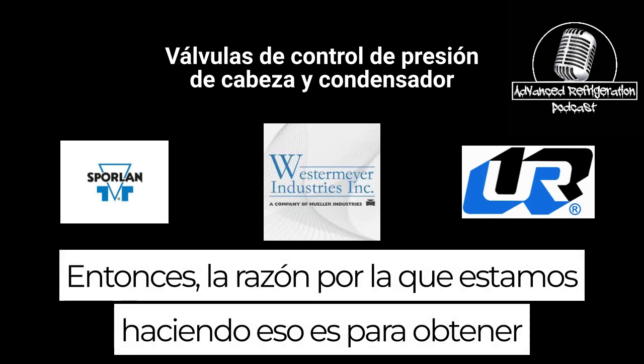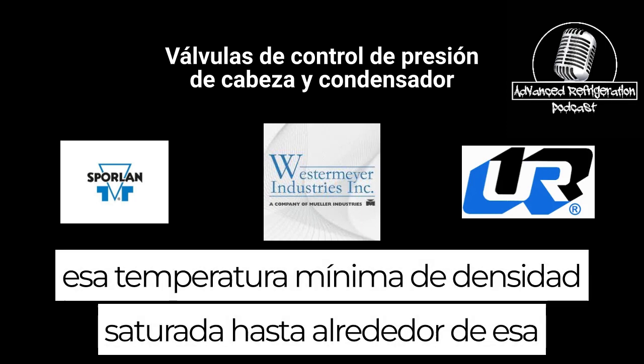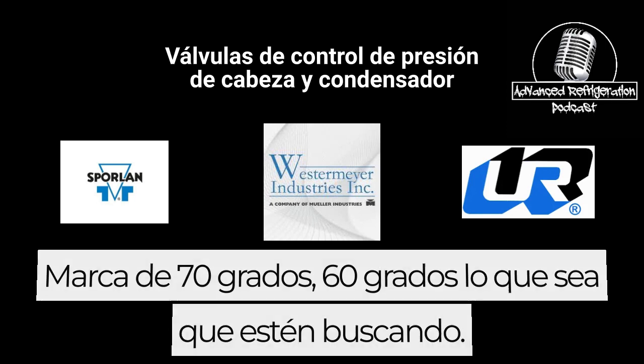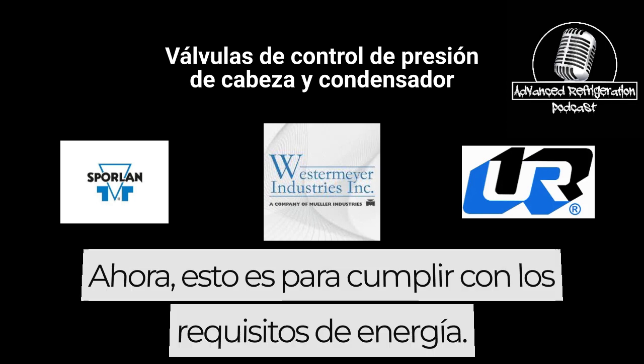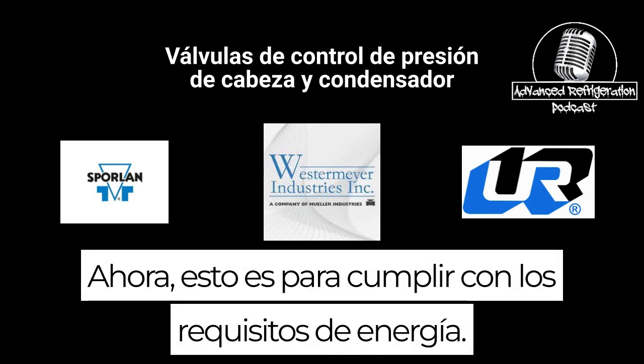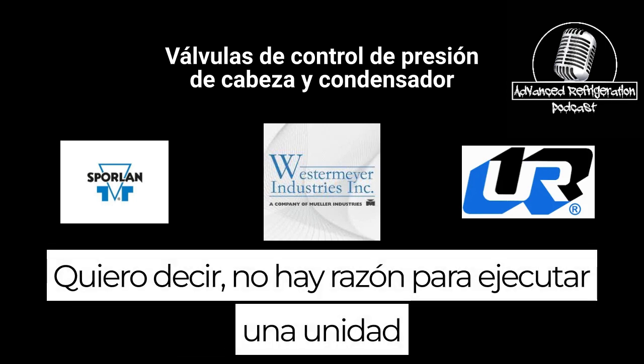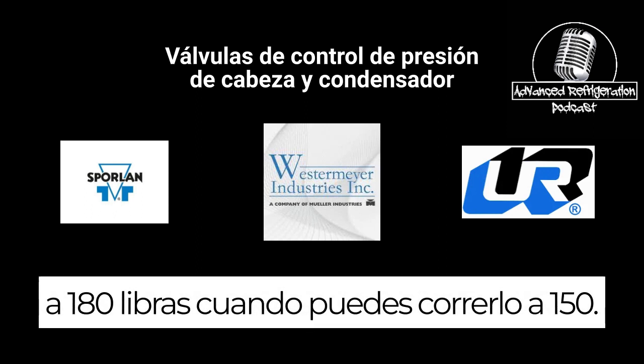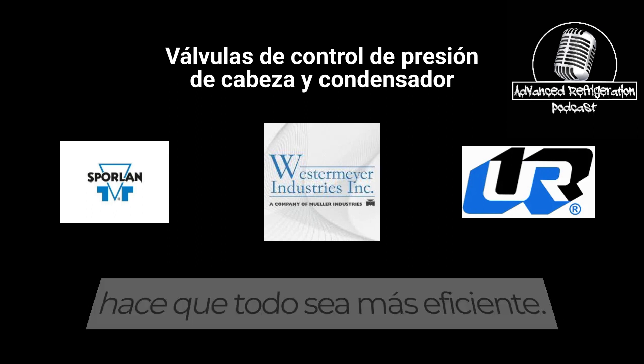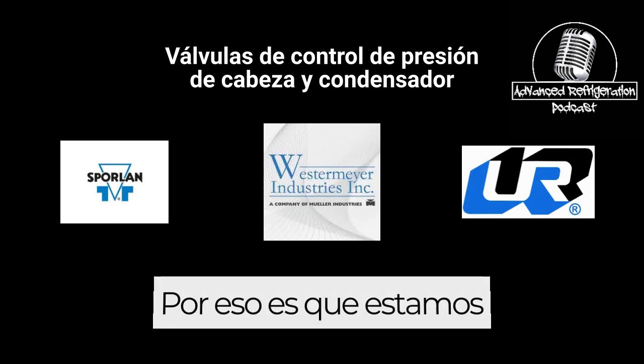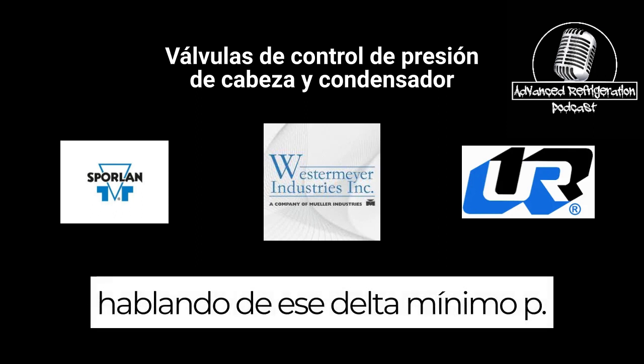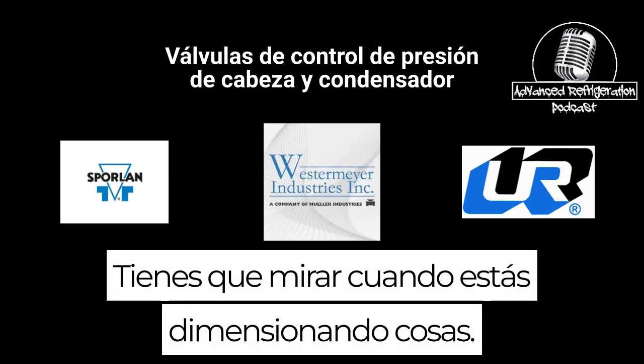The reason we're doing that is to get that minimum saturated condensing temperature down to around that 70 degree mark, 60 degree, 50 degree, whatever they're going for. Now, this is to meet energy requirements. I mean, there is no reason to run a unit at 180 pounds when you can run it at 150. You're just saving energy and it makes everything more efficient. So this is why we are talking about that minimum delta P. You've got to watch when you're sizing stuff.